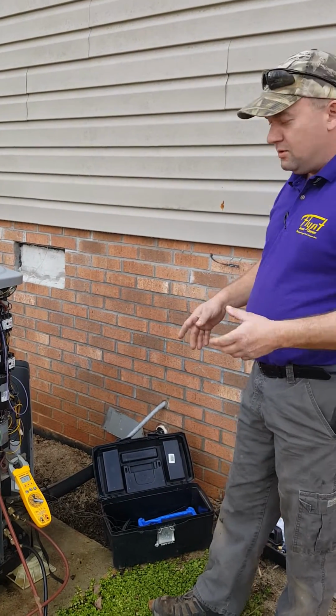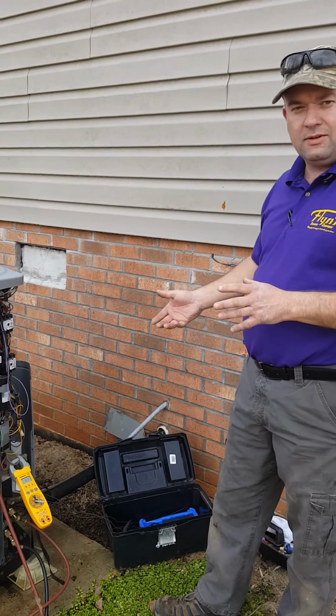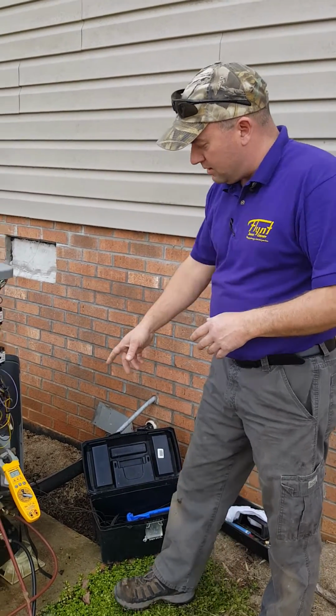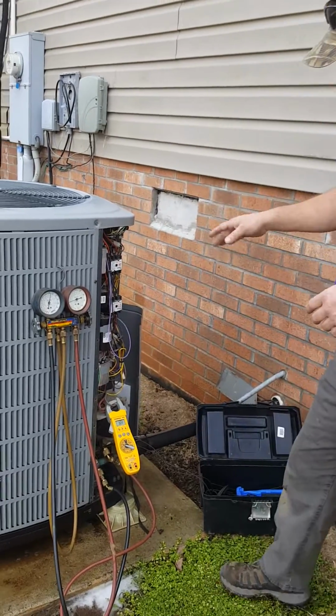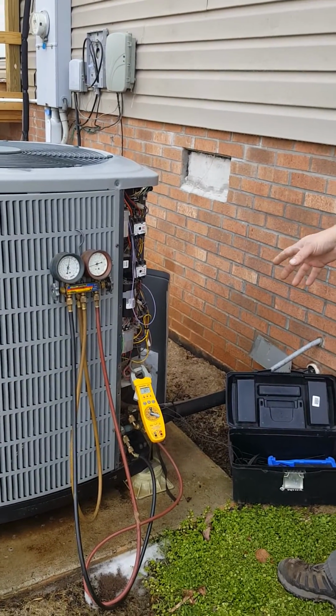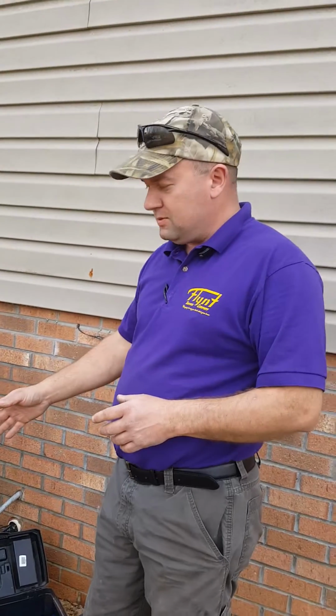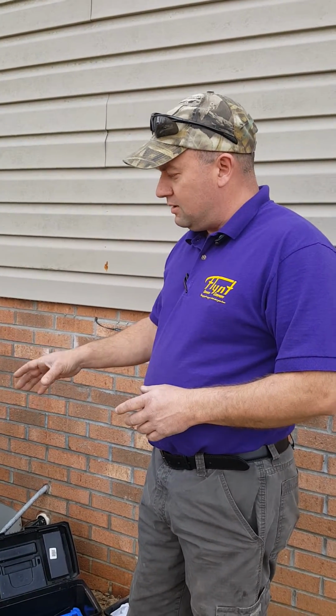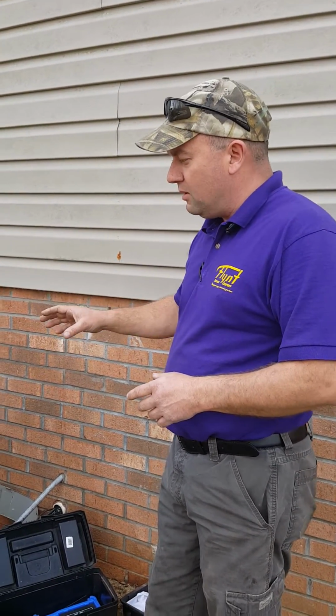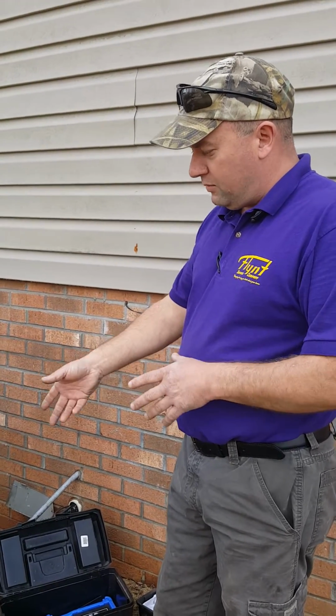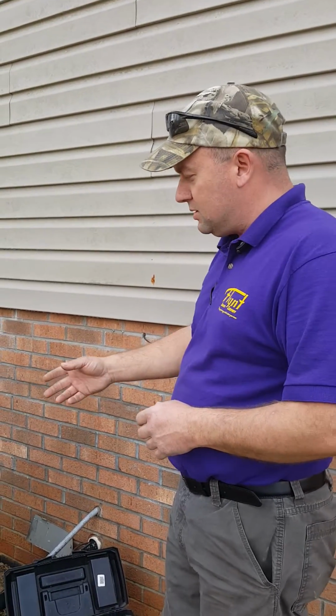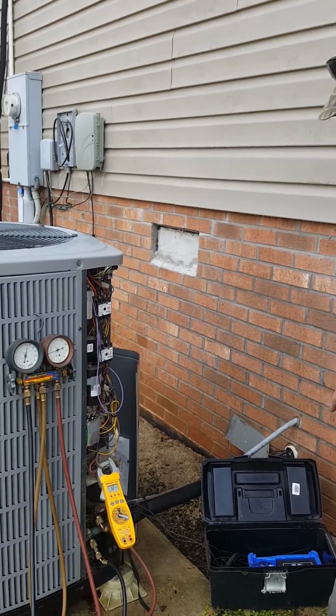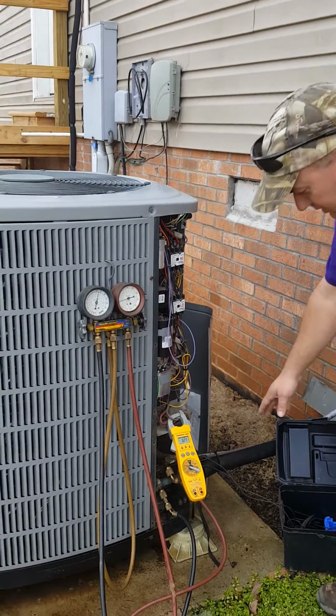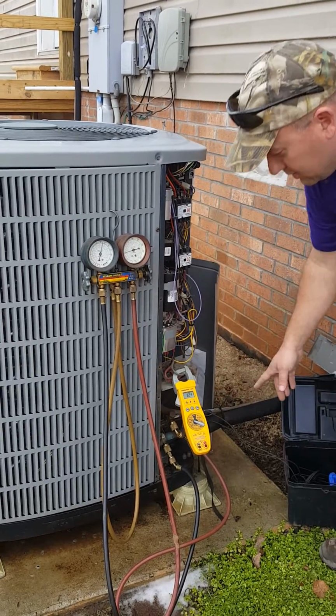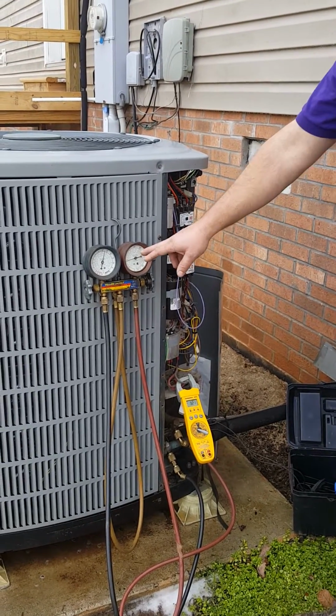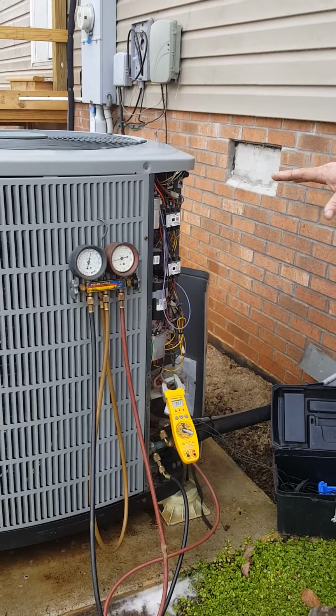The last thing we're going to do is cut everything on and let it run about 15 to 20 minutes. We're going to hook an amp probe up to the main wires coming into the unit and look at the amperage. This unit is running at 3.2 amps. That gives us a little more indication of the condition of the compressor and the outdoor fan motor. I've also hooked my refrigerant gauges up to it. This is an R22 system. I've also hooked up my superheat kit, with line temperatures on the liquid line and the suction line, and both of my lines hooked up on my gauge manifold.